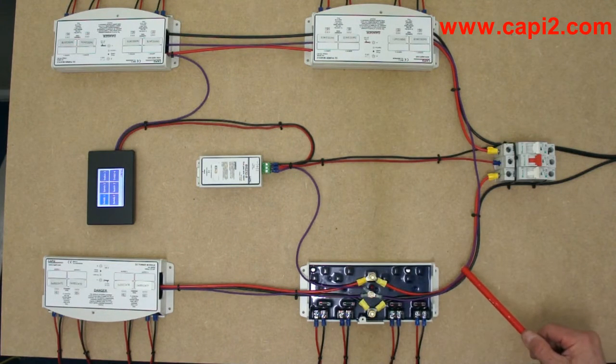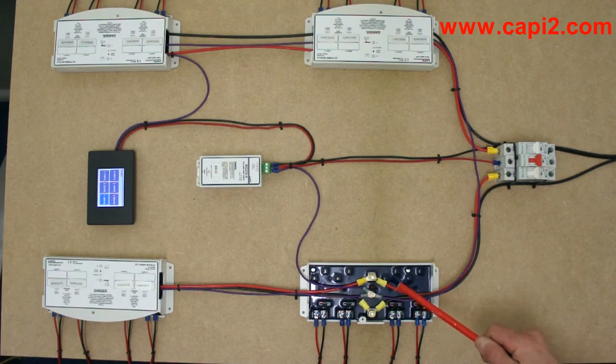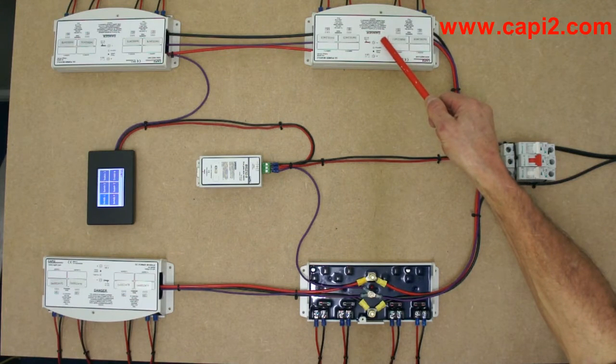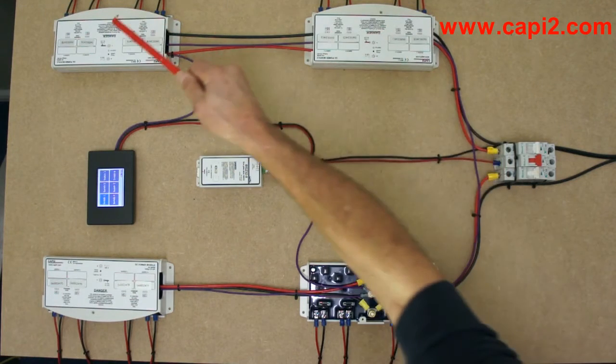Here we have the second harness, including the communication cable. The harness is connected to the power modules with 6 mm bolt connectors. The modules can be placed in series after each other. The modules should be located close to the consumer. Here we are choosing 4 different locations. This gives a minimum amount of cabling.